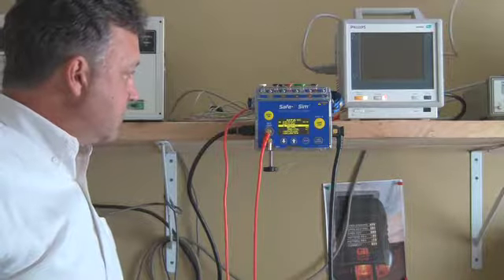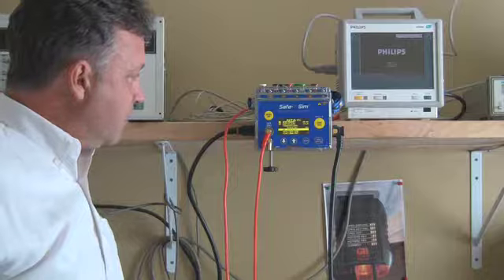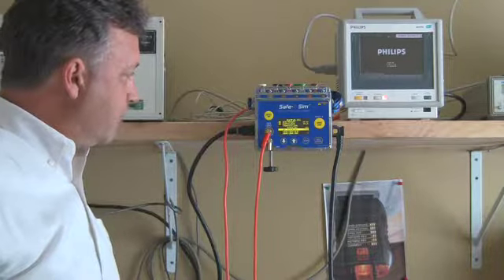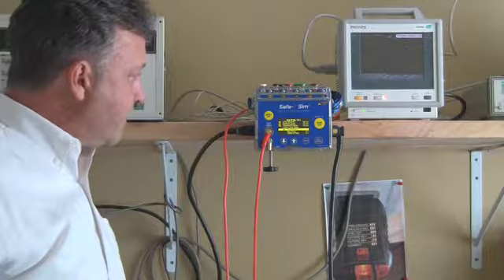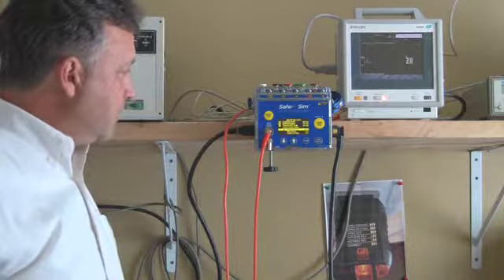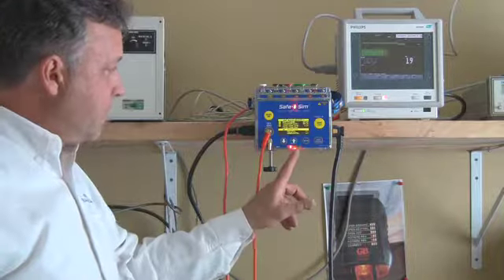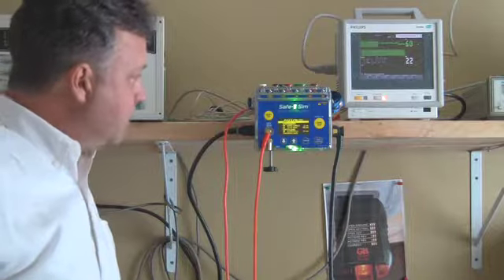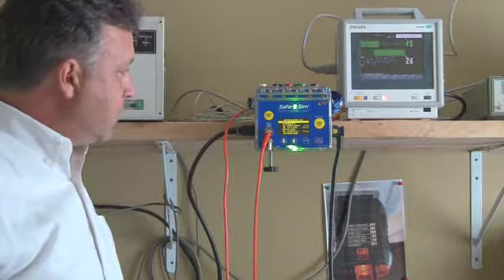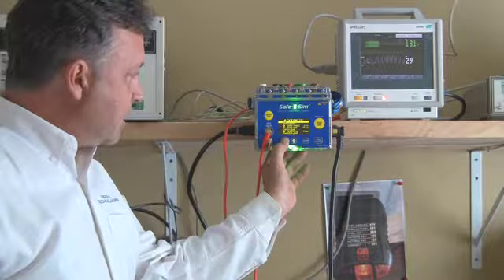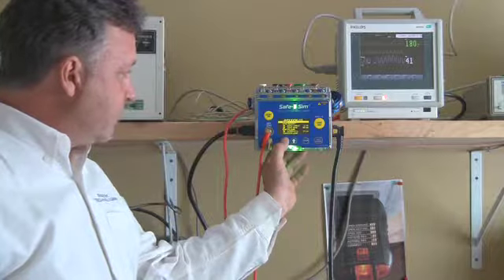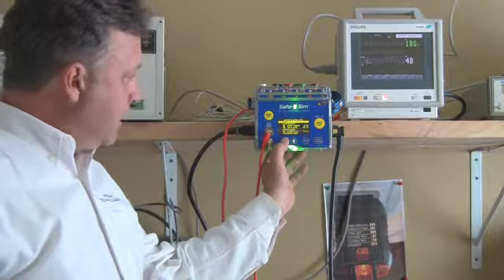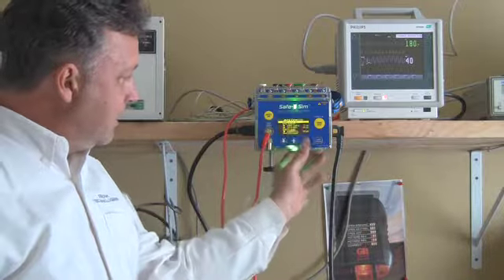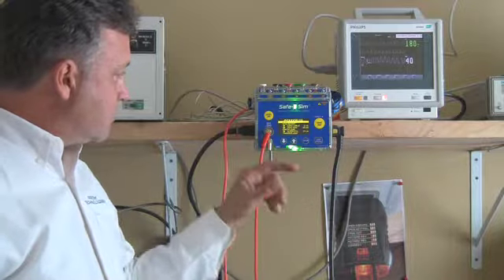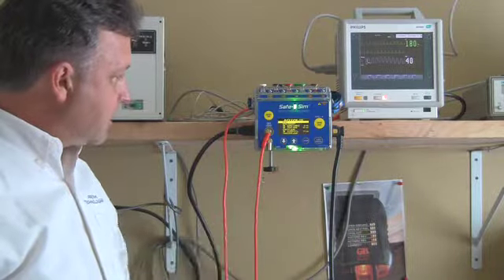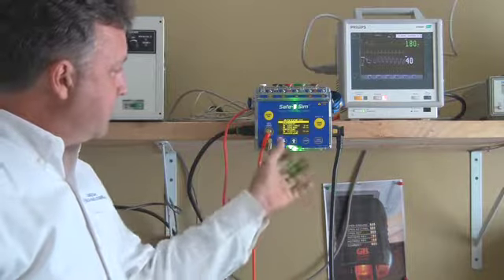So this is an automated test that I named ES2. And you can see here it's moved on to earth leakage. Now it's on to chassis leakage, ground open. And it's giving us a green flash at both LED points for each test, telling us that it's passing those tests. Quick red flashes tells us that it's in ISO. So it's doing the ISO test on the snaps. And we're done. Quick and easy. I had set up the profile ahead of time so you could see 4 different individual tests run under automation. And at the end, you get a solid green LED both at top and bottom. You can actually see it from the sides as well. And solid green tells us that every one of the tests passed and that we completed the testing.